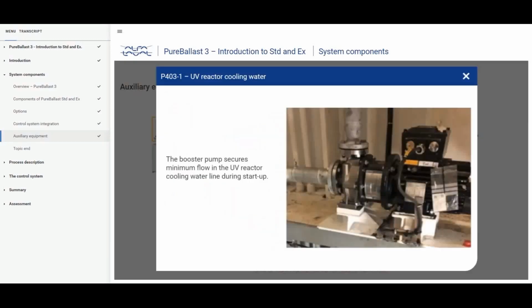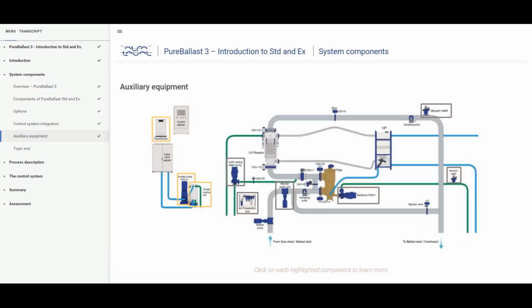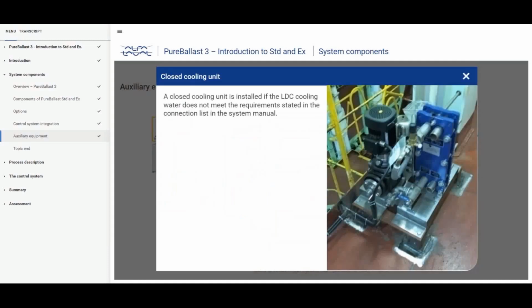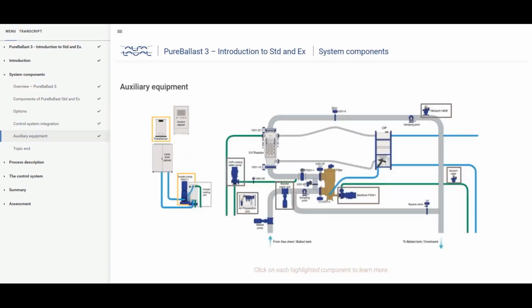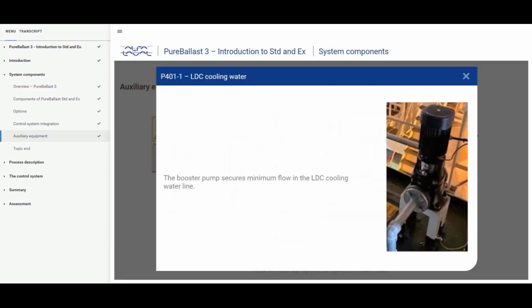The booster pump secures minimum flow in the UV reactor cooling water line during startup. A closed cooling unit is installed if the LDC cooling water does not meet the requirements stated in the connection list in the system manual. The cooling unit circulates a closed loop of fine quality water which is cooled with the normal seawater cooling system. Booster pump P401-1 is included. The booster pump secures minimum flow in the LDC cooling water line.